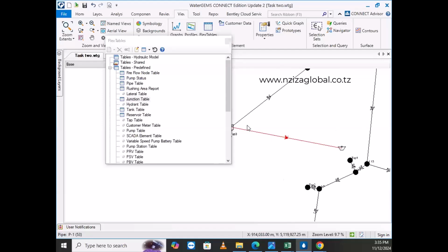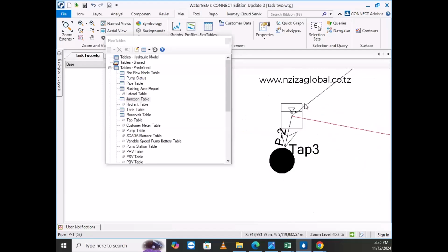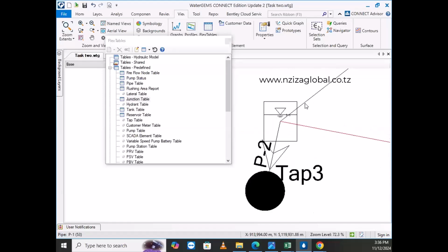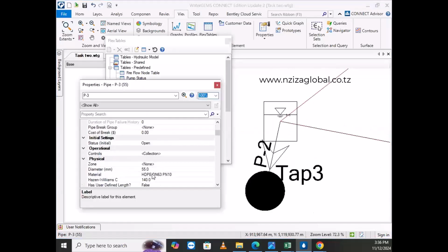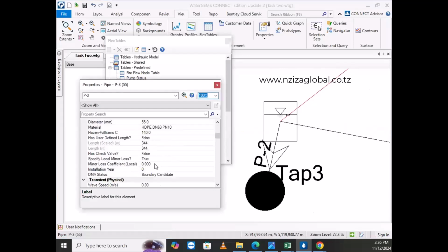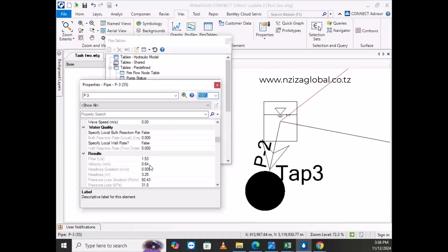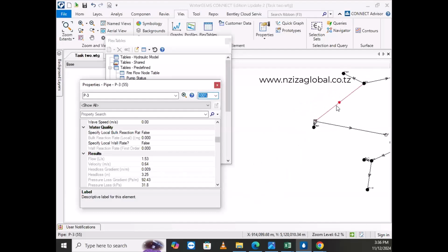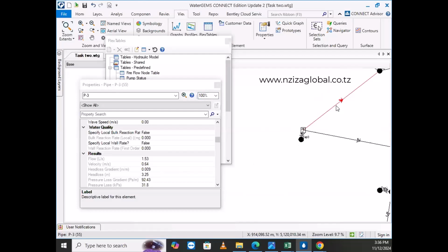As we have 1.7, you may ask yourself, if I put that in a pipe of, for example, 63, is it okay or not okay? If I take this Q and put it into these pipes, will the velocity be okay or wrong? It will be okay. Then let's use the pipe of 63. Now we have the diameter.